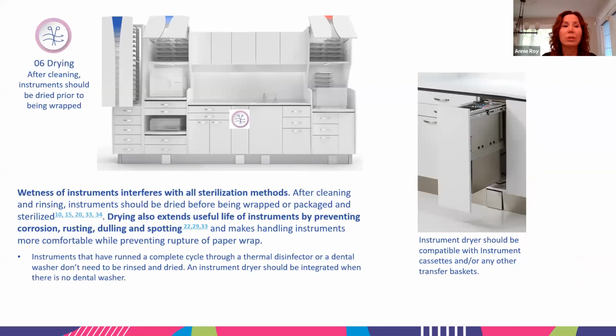After rinsing, you need to dry those instruments because wetness of instruments can interfere with all sterilization methods. Drying also extends the useful life of instruments by preventing corrosion, rusting, dulling, and spotting. It makes handling instruments more comfortable and it prevents rupture of paper wrap. If you're using a dental washer, you do not need to rinse and you do not need to dry. But if you're using a standard ultrasonic cleaner, it is recommended to integrate an instrument dryer in the Steri Center.